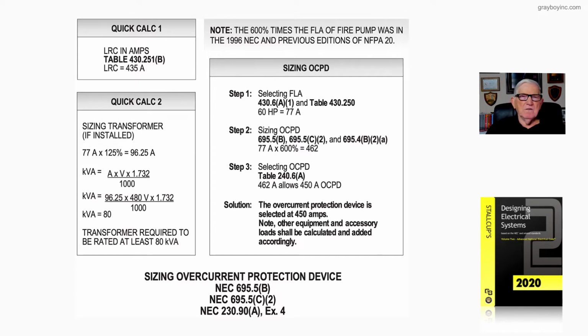Notice in the note the 600% times the full load amps of the fire pump was in the 1996 NEC and previous editions of NFPA 20. So in this illustration, just for the sake of giving you an example, we use the 600%, but you always want to size the overcurrent device that allows the fire pump to operate to failure.